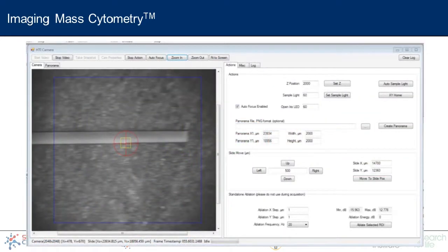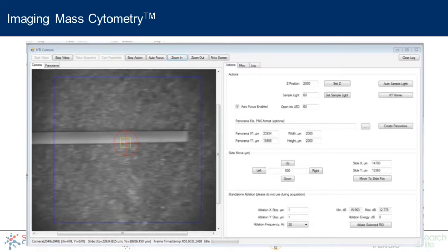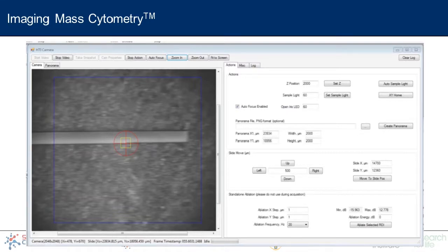The laser ablation spot size is about one micron. The laser fires, ablates approximately one micron-squared of tissue, and the material flies up into the CyTOF for measurement. Then the adjacent spot is ablated, and this continues — rasterizing the entire area of tissue we want to image at about 200 shots per second. This all happens automatically, moving left to right, then stepping down a line, allowing us to let it run overnight.